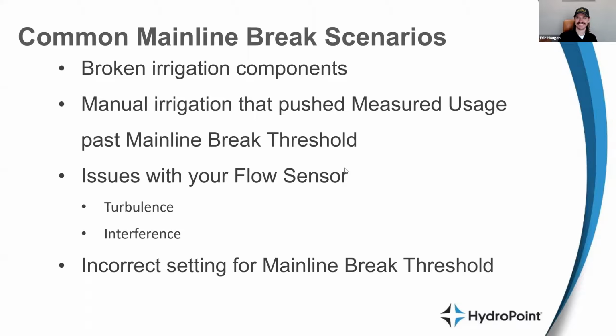So that's all the details and some of the common scenarios, right? We've talked about. And most of the time, it doesn't necessarily mean that there's a mainline break, but that's what we always want to be vigilant about. We always want to make sure that it's not that. But any sort of broken components can drive you past that measured flow value, that threshold, right? It just is a limit that gets passed. And so any sort of breaks, lateral breaks can do that. Stuck valves can do that. Broken heads. Do you have any tips or tricks on responding out and things that people should look for when they're responding to these breaks?